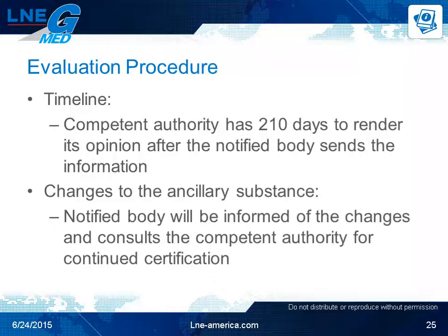Let's talk about changes to the ancillary substances. Where changes are made to an ancillary substance incorporated in the device, in particular related to its manufacturing process, the notified body shall be informed of the changes and shall consult the relevant medicines competent authority, for example, the one involved in the initial consultation, in order to confirm that the quality and safety of the ancillary substances are maintained.